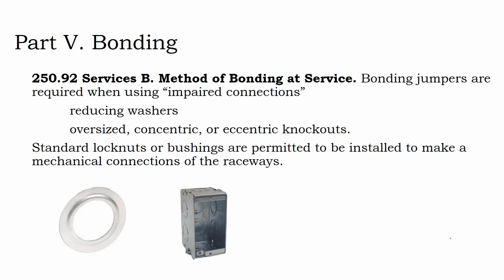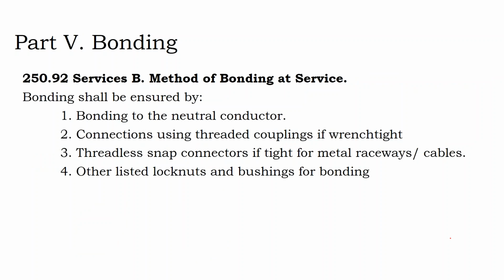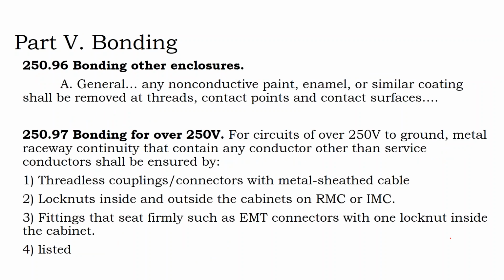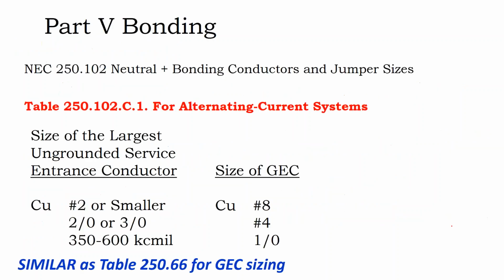So metal parts need to be bonded. We've talked about the concentric knockouts. It's kind of moving us towards our wiring discussion. There may be some additional connections that are required for higher voltage components. So what's common is to use metal conduit with compression connectors and lock nuts. There are sizes for that bonding jumper on the neutral. We'll have a picture of it a little bit later, but there are minimum sizes for that.